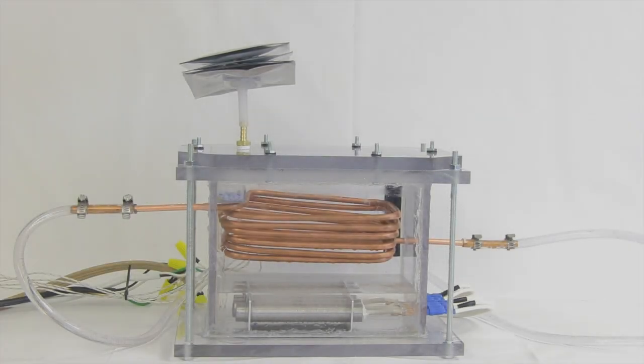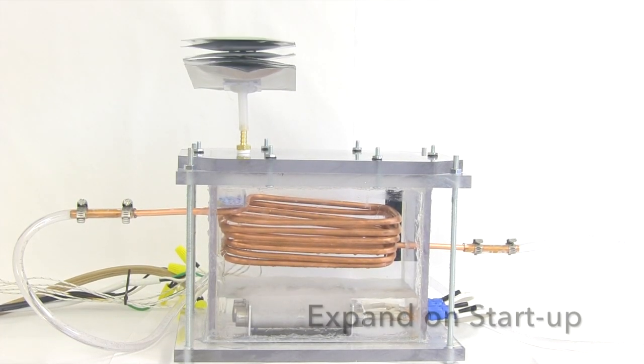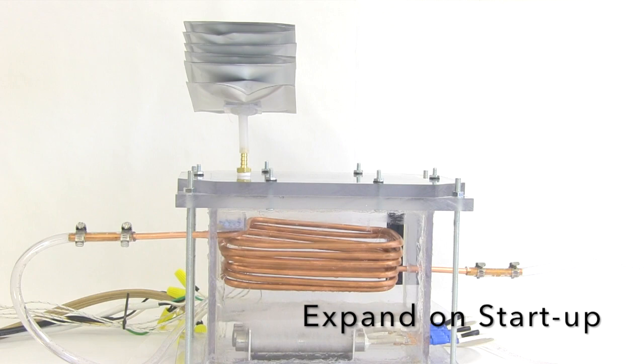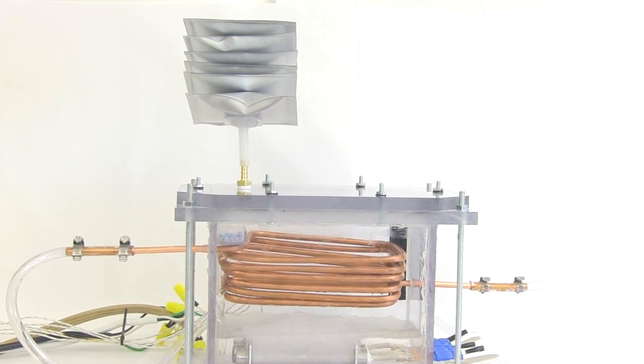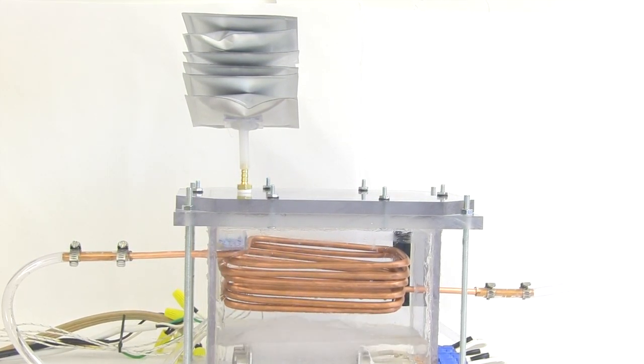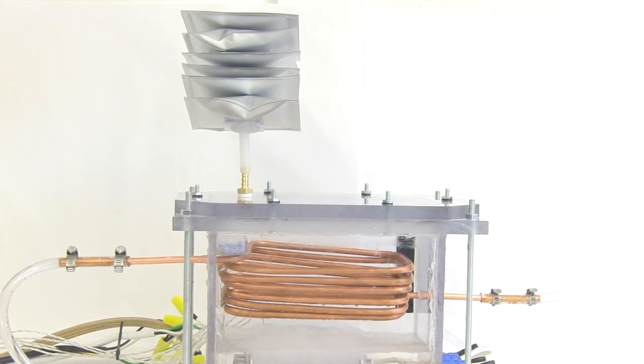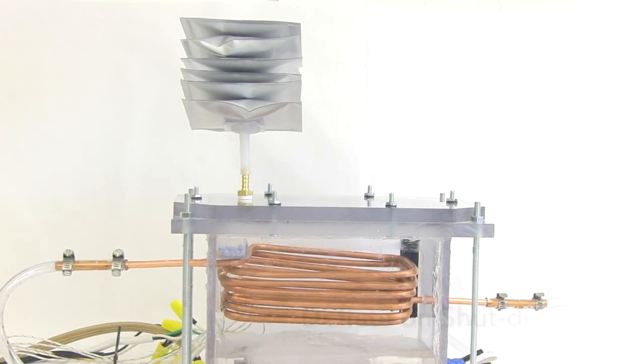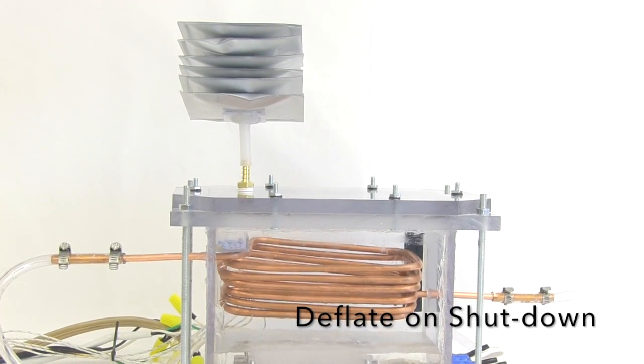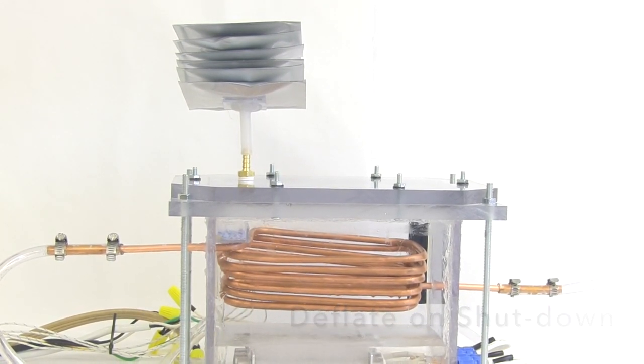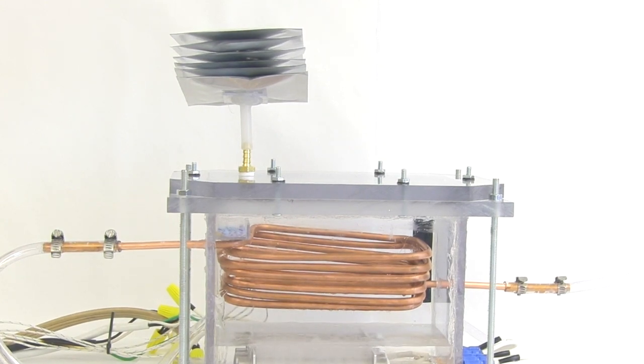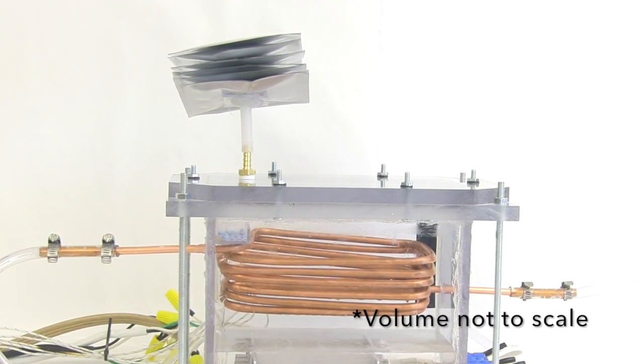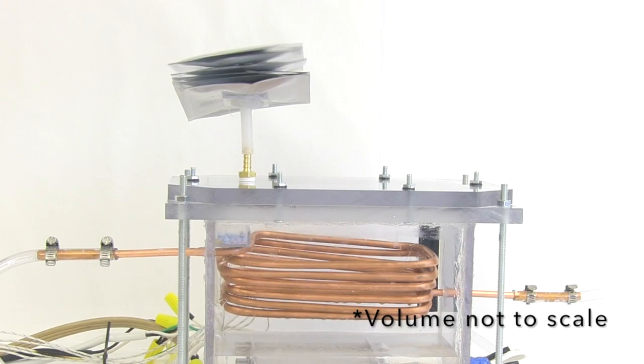Another way to mitigate fluid loss is to use bellows. Although this method is not as spatially accommodating, no fluid is lost using this method. A bellows is an inflatable bag which contains the tank's excess air while maintaining the system's pressure. As the fluid begins boiling, the air, which usually is pushed out by the rising vapor level, is instead pushed into the bellows, not allowing the vapor to escape, so no fluid is lost. The main issue with this technique is that the bellows must be anywhere from 1 to 2 times the tank volume.